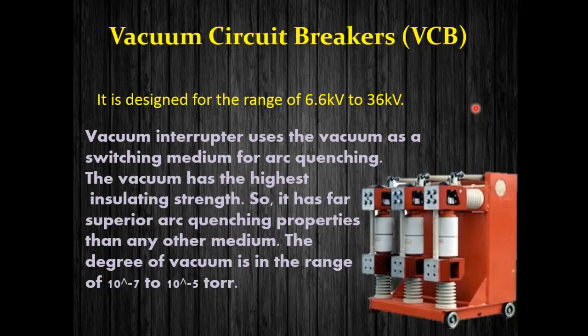The vacuum circuit breaker (VCB) is extremely popular for voltage ranges between 6.6 kilovolts to 36 kilovolts. The vacuum interrupter uses vacuum as the arc extinguishing medium. Vacuum has the highest insulating strength since it does not contain any molecules of air, giving it far superior arc quenching properties than any other medium. The degree of vacuum is in the range of 10⁻⁷ to 10⁻⁵ torr.